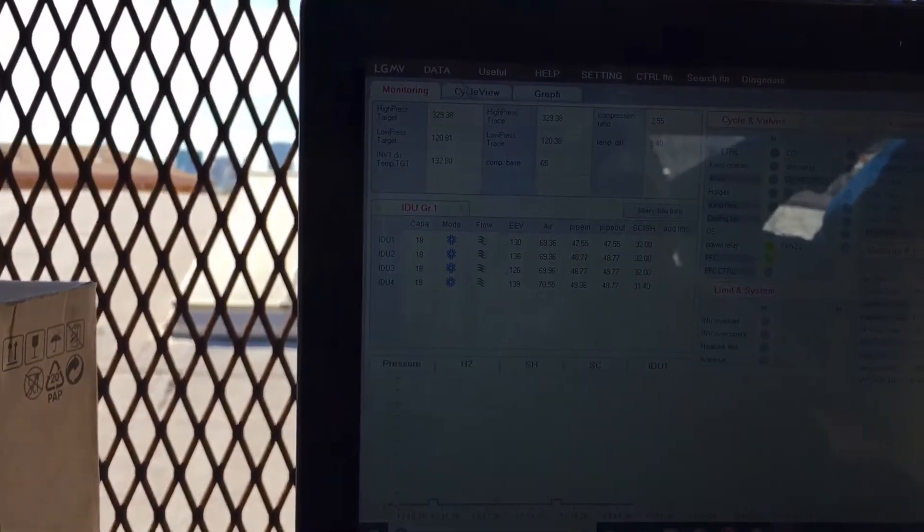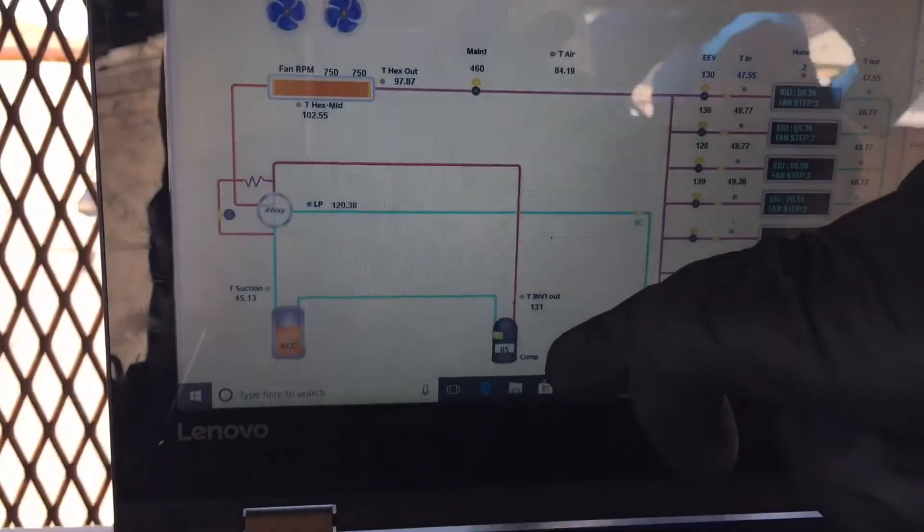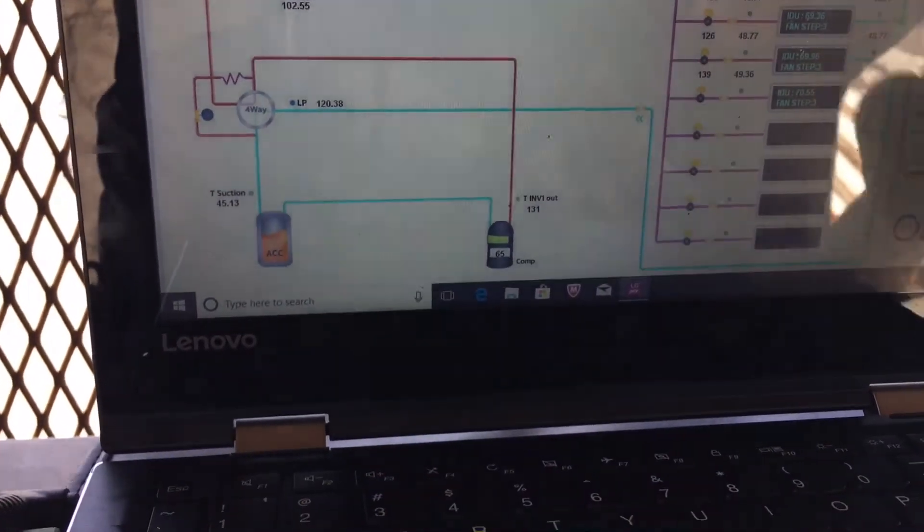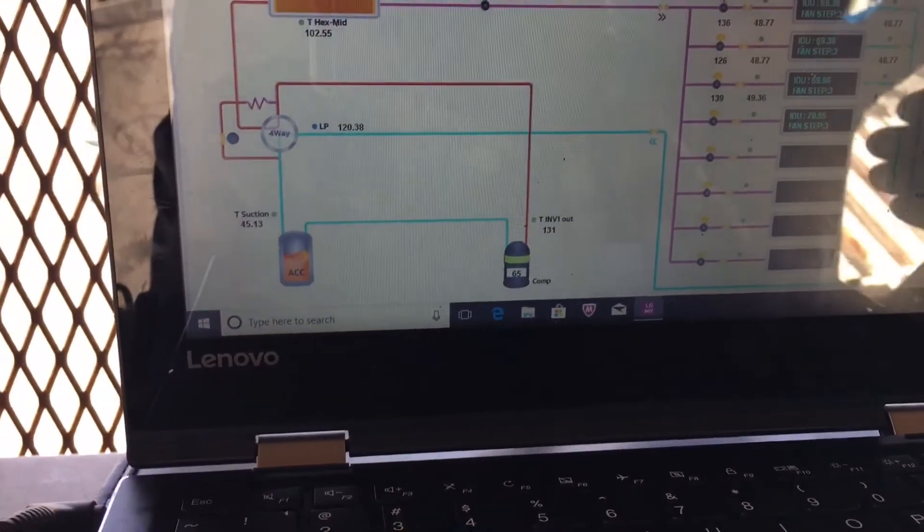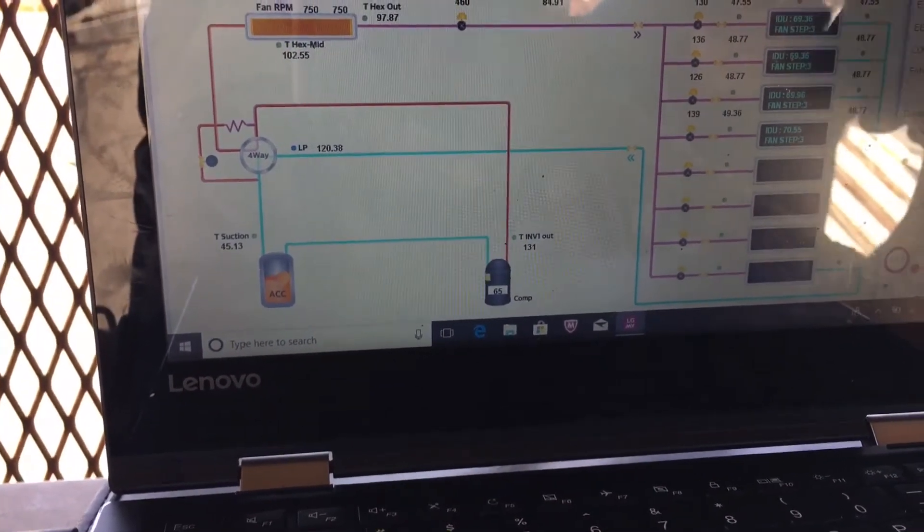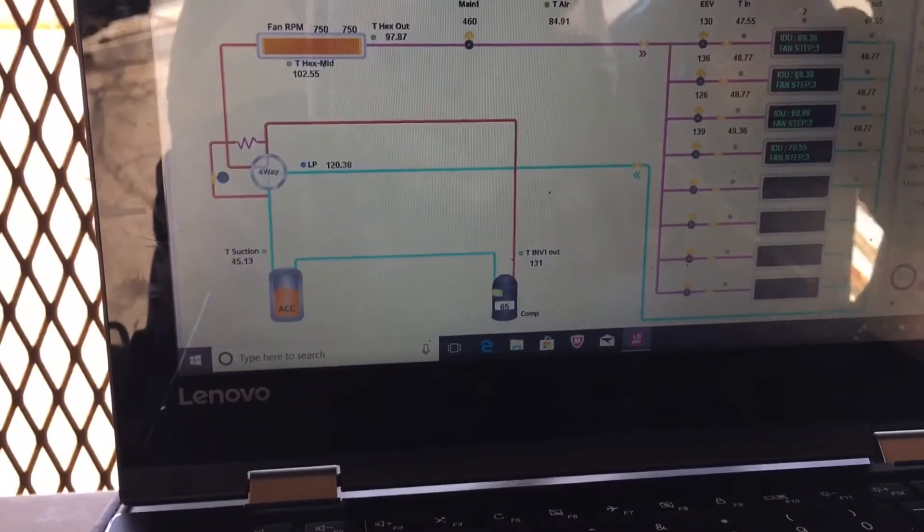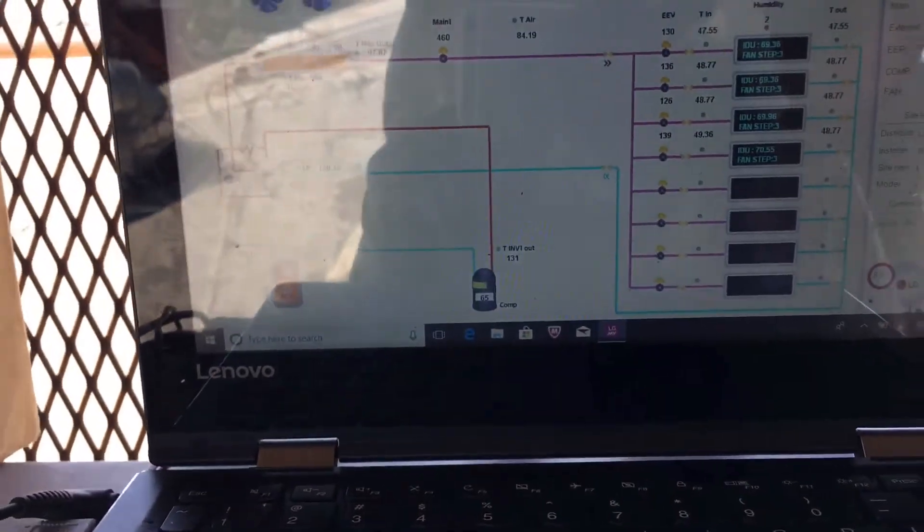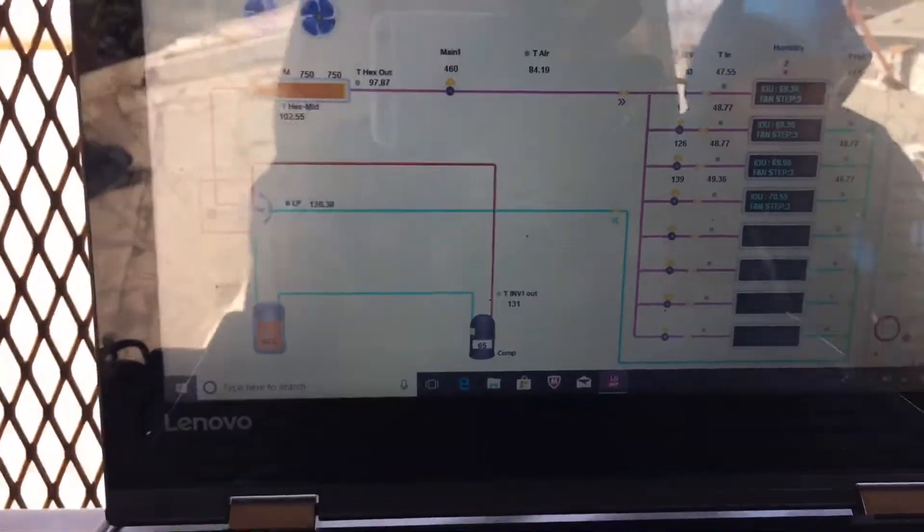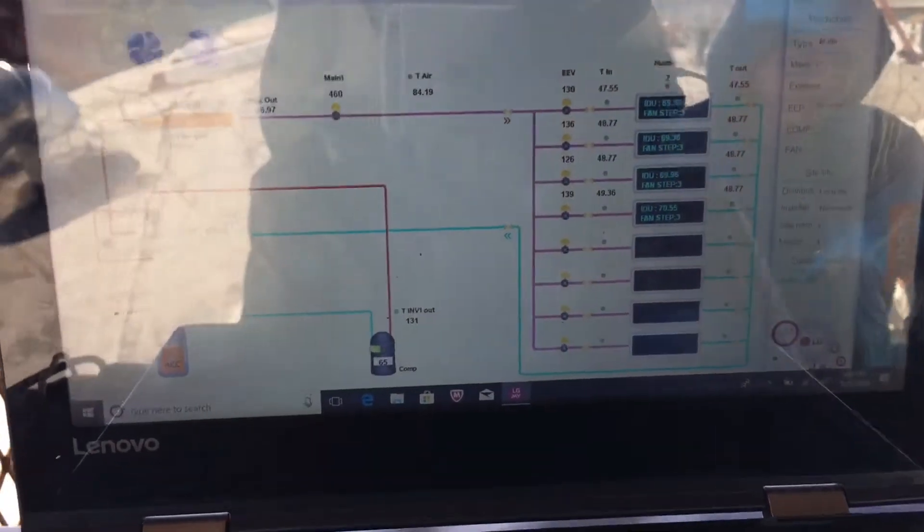Here's your subcooling. Let's go to cycle view. Okay, so here's your cycle view. We're running our compressor at 65 Hertz right now, so we're overdriving because the unit is trying to be forced to catch up. Because I have the temperature selector set so low, it wants to overrun to catch up, and then once it satisfies, it'll start tapering off all by itself. You see that thing go all the way down to 20.